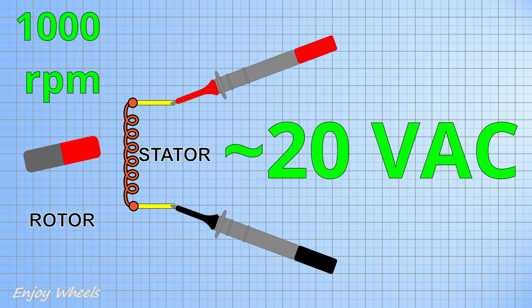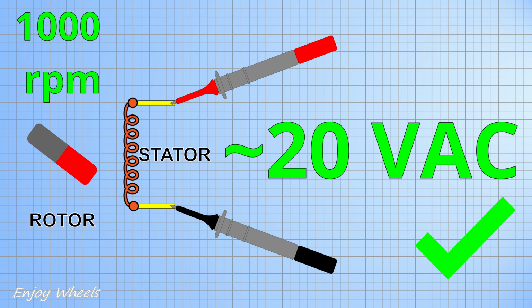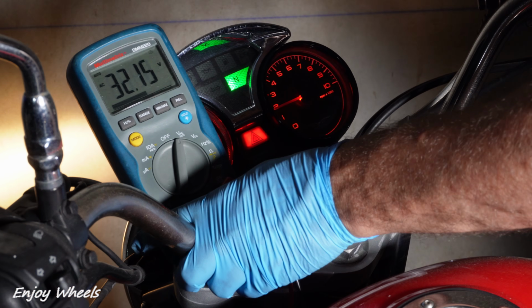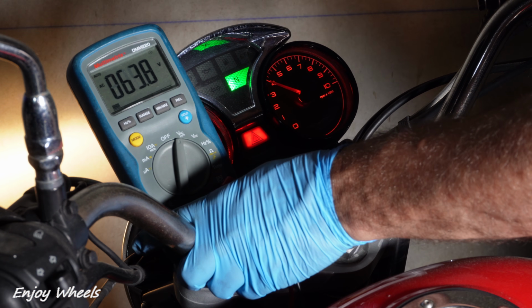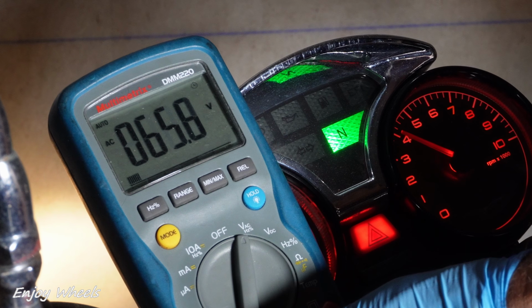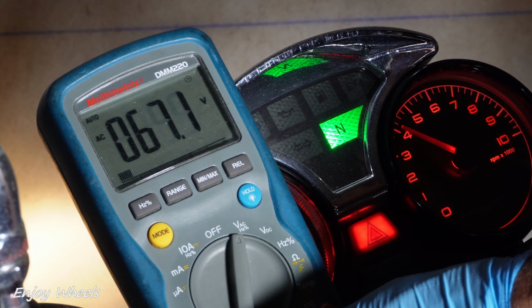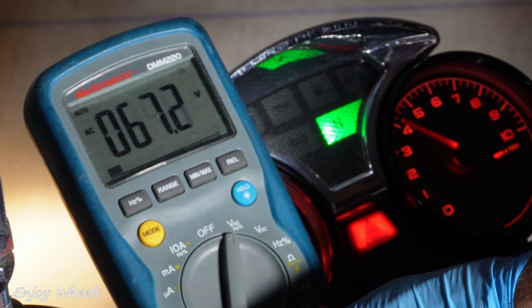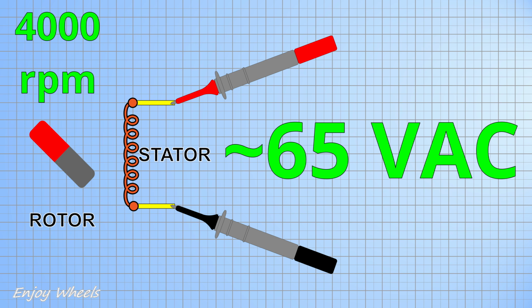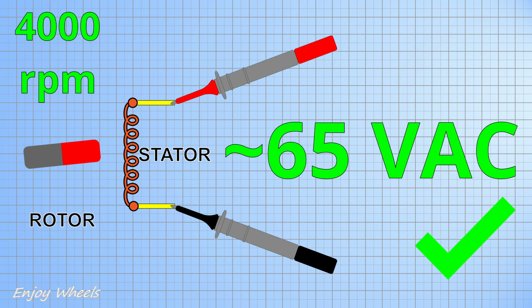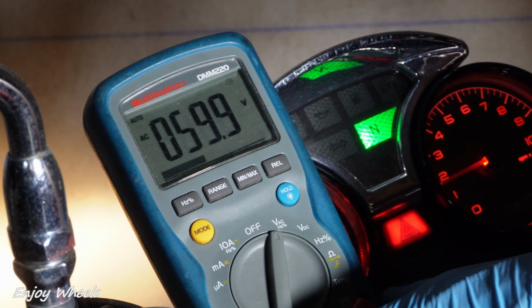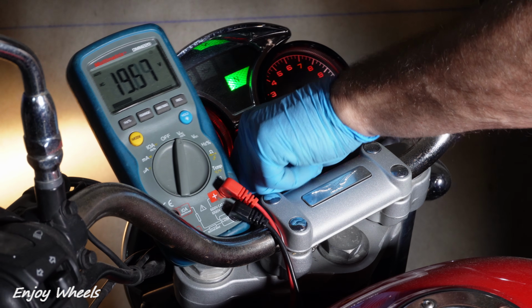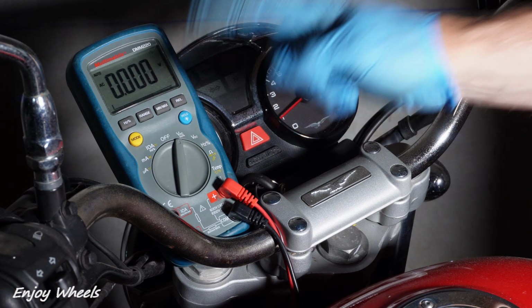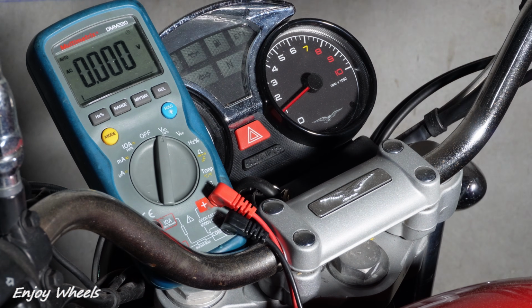The service manual says 20 volts AC. Perfect. At 4000 revolutions per minute I get between 64 and 67 volts AC. The manual says 65 volts AC at 4000 revolutions per minute, so we're good here too. We can now conclude that both the stator and rotor are good.